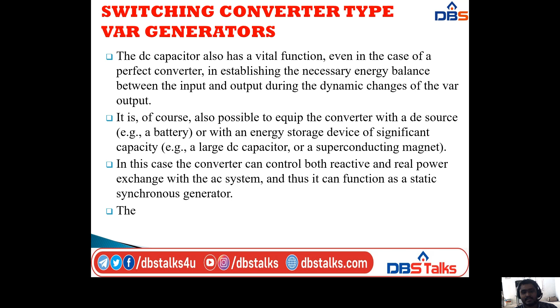The capability of controlling real as well as reactive power exchange is a significant feature which can be used effectively in applications requiring power oscillation damping, leveling peak power demand, and providing uninterrupted power for critical loads. This capability is unique to the switching converter type VAR generator, and it fundamentally distinguishes it from its conventional thyristor controlled counterpart.